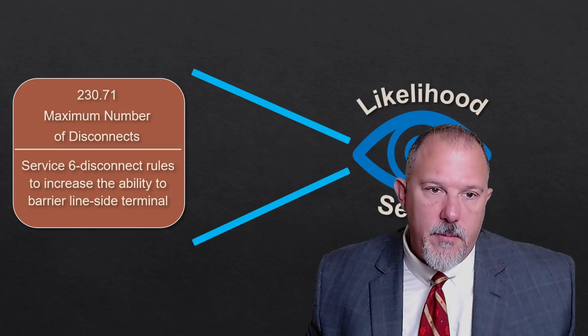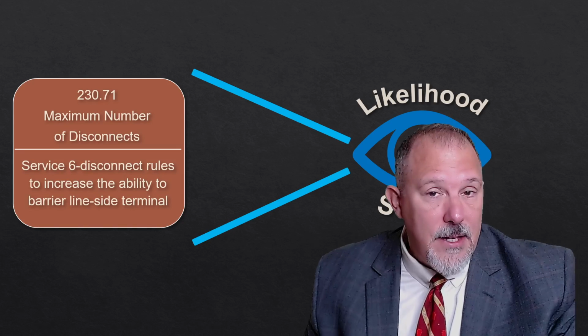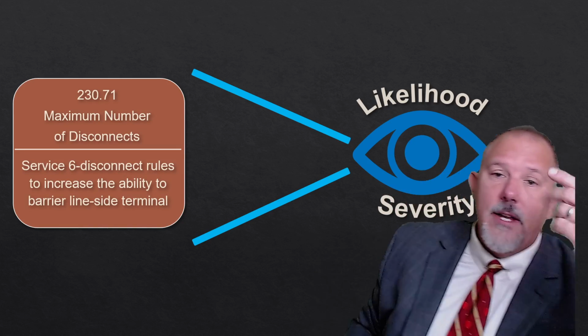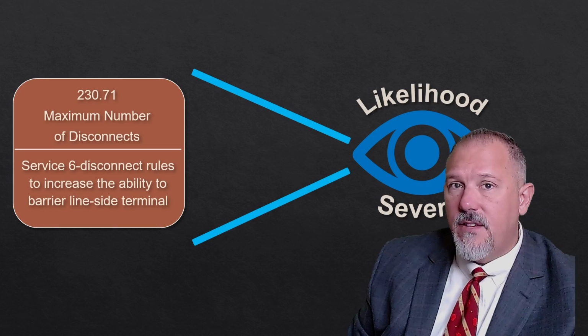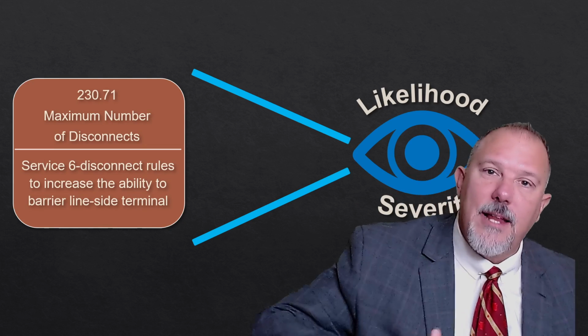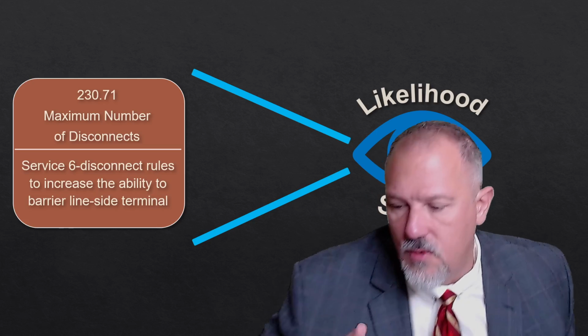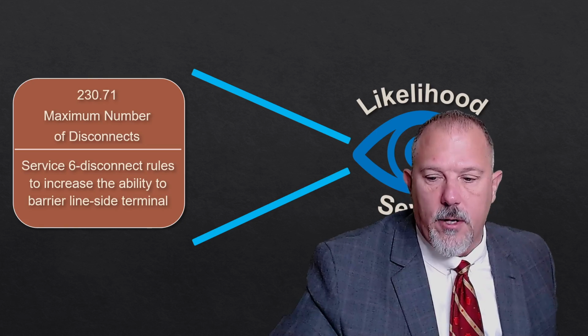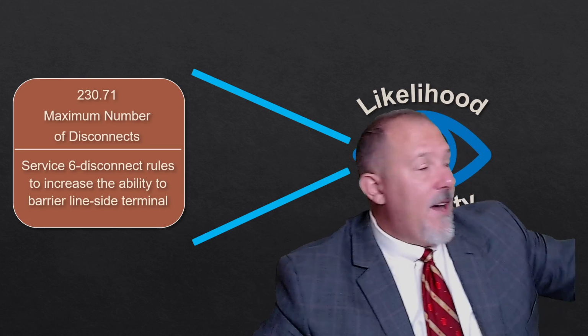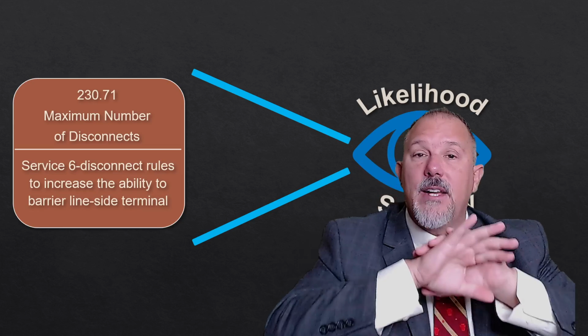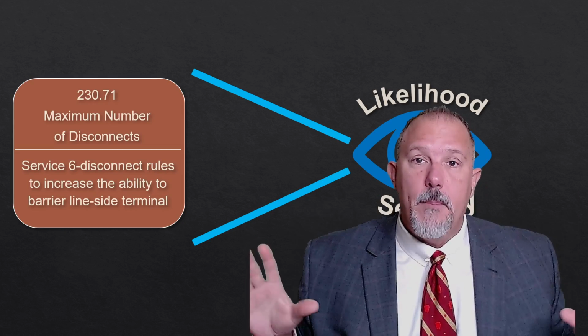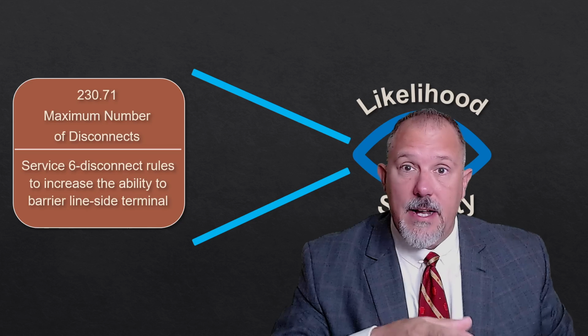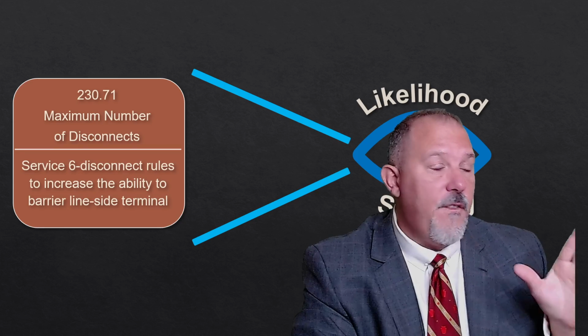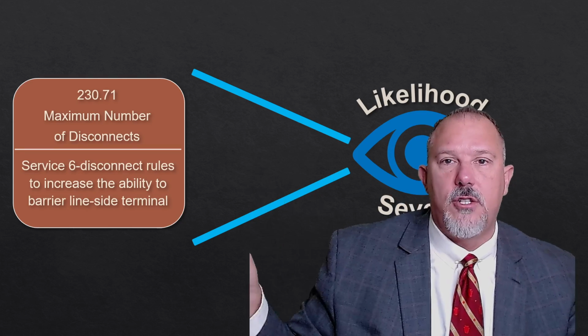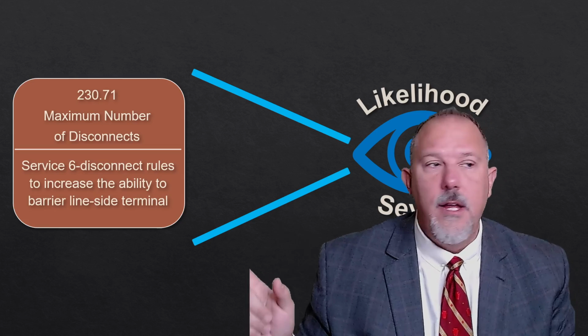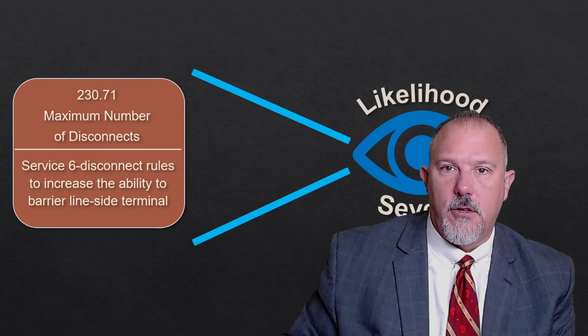230.71, maximum number of disconnects, helps. I think it might help do a couple things. It could help in both of these, likelihood and severity. Because why? Establishing an electrically safe work condition. What are some of the reasons why you can't establish an electrically safe work condition? If you have to turn off a system that impacts a wide area in the plant, they may say, it's fine, you can shut this down if it didn't control this process over here, because if you shut that process down, then I create a hazard for all of these other people.